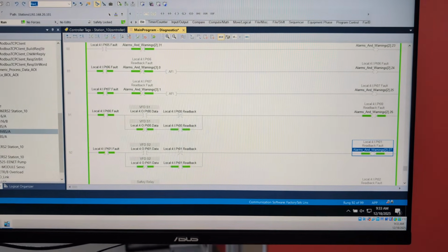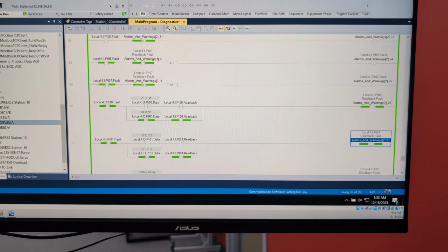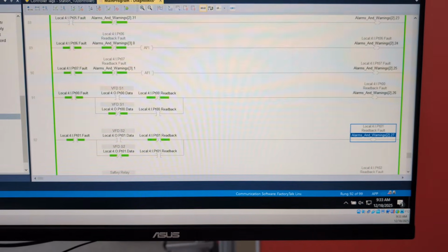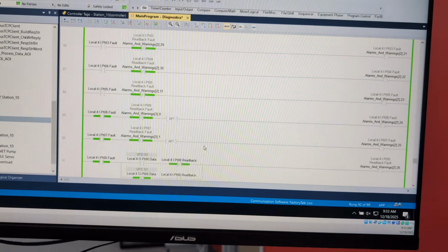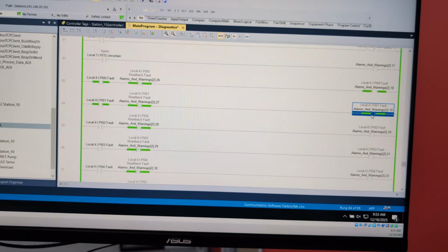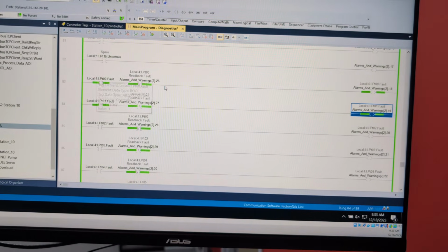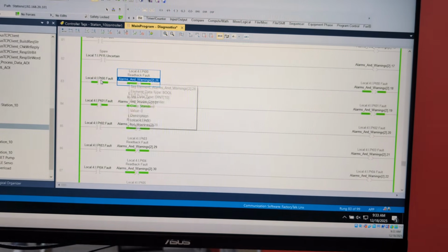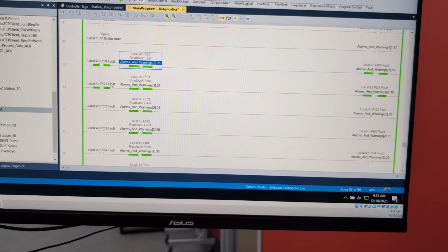So I can fix the alarm. First thing I'm gonna do while we're staring at this is fix this alarm, and we're gonna see what changes. All right, so our alarms drop out. We should be super happy now. But now if we scroll up, we still have our general alarms on them. This is probably the piece I've overlooked every time we've tried to run this fault exercise. So now the question is, why are we still faulted?